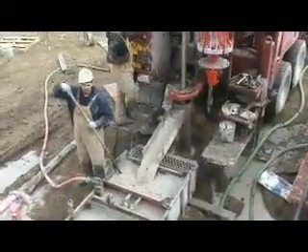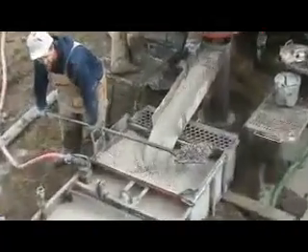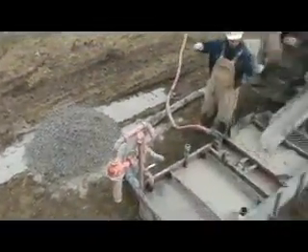Durbin Geothermal presents Mud Rotary Drilling. Mud rotary drilling is the most common method of installing ground source heat pump loops throughout the Midwest and pretty much anywhere where bedrock conditions are not present.